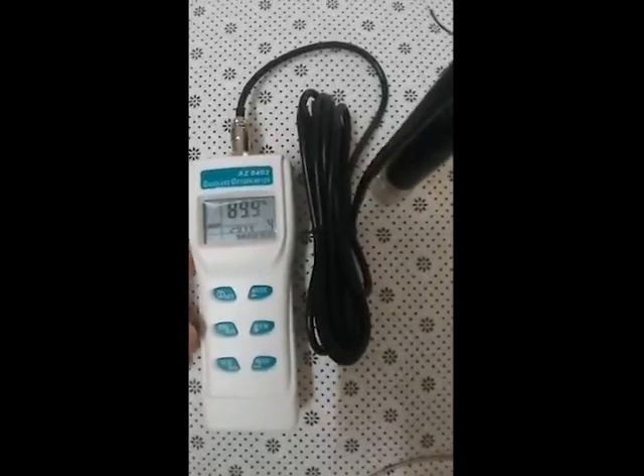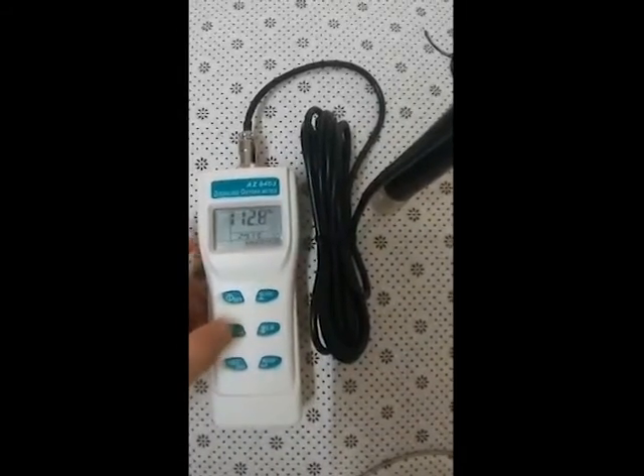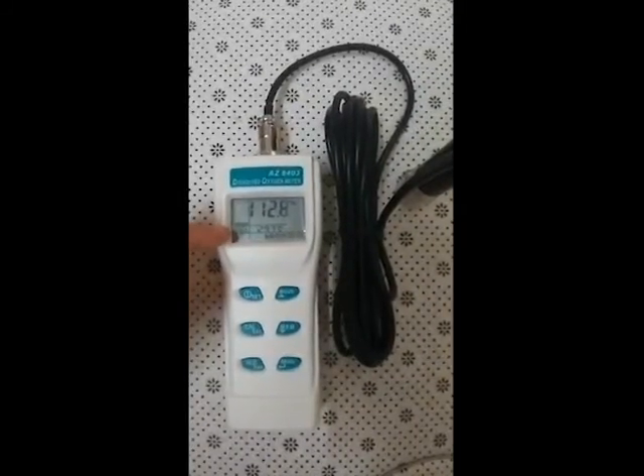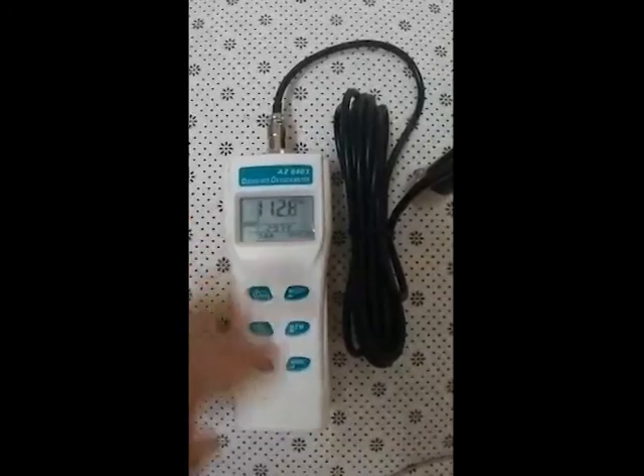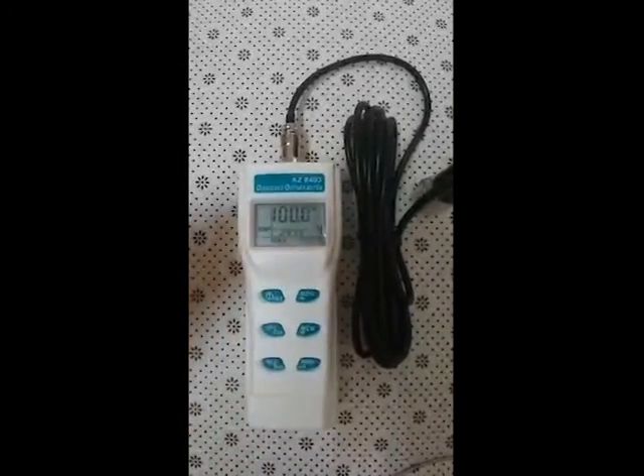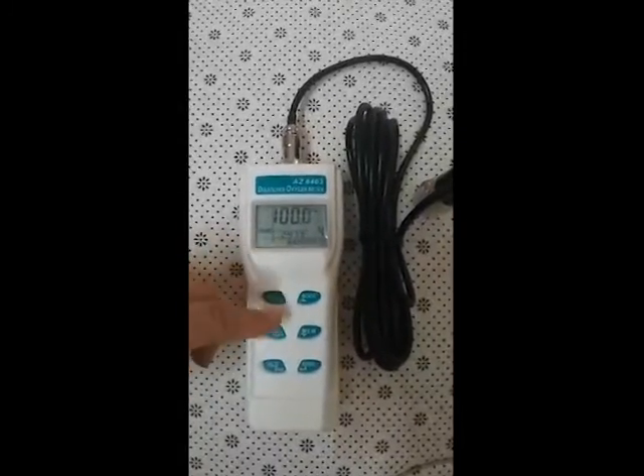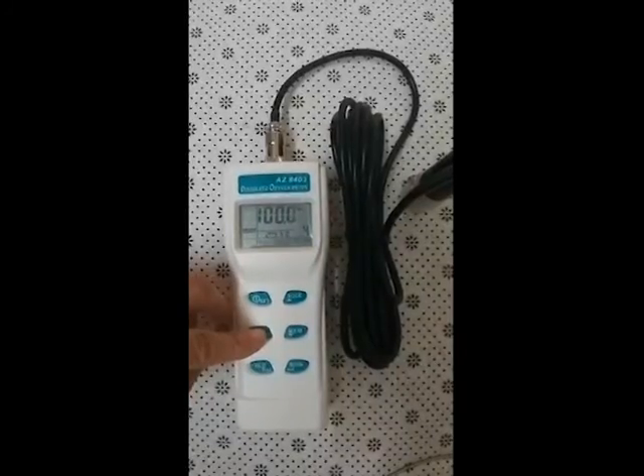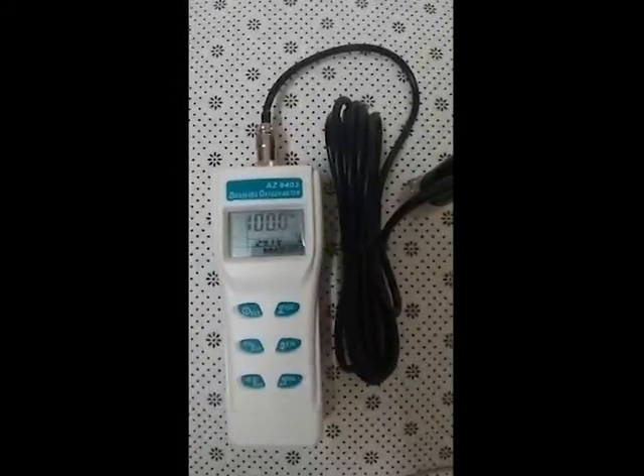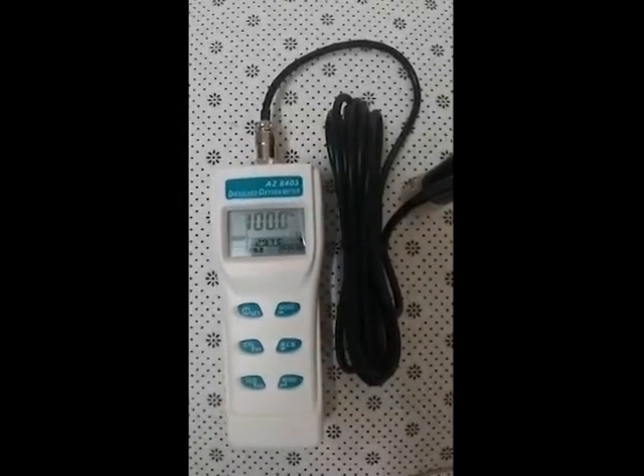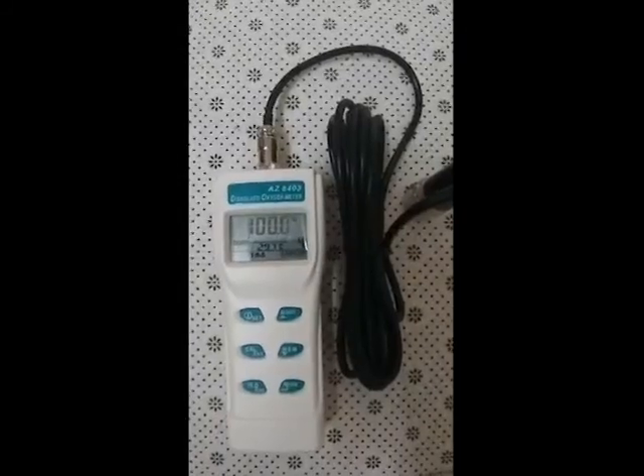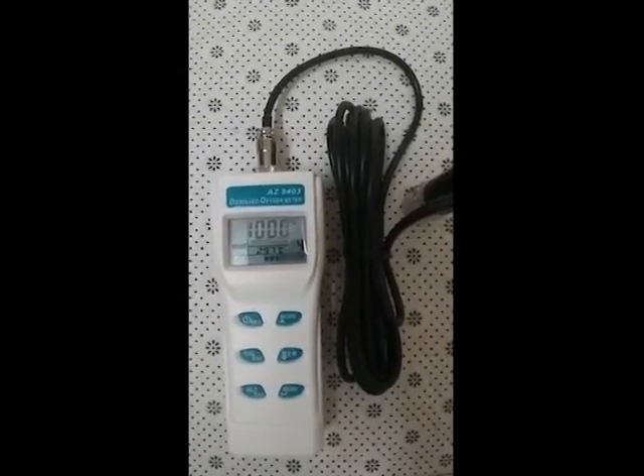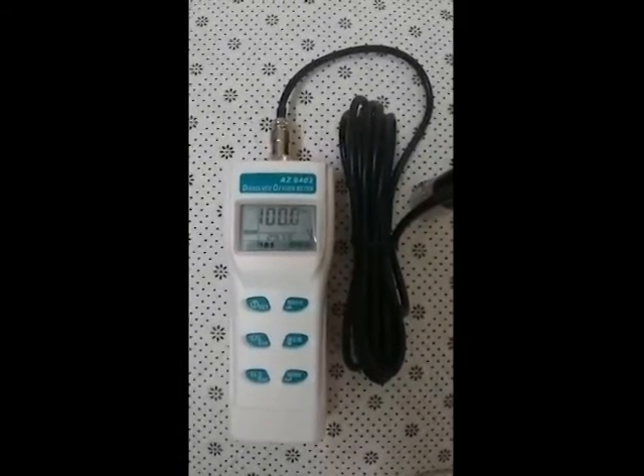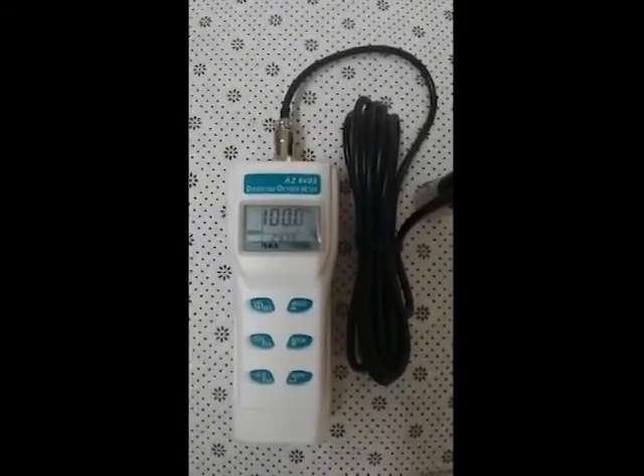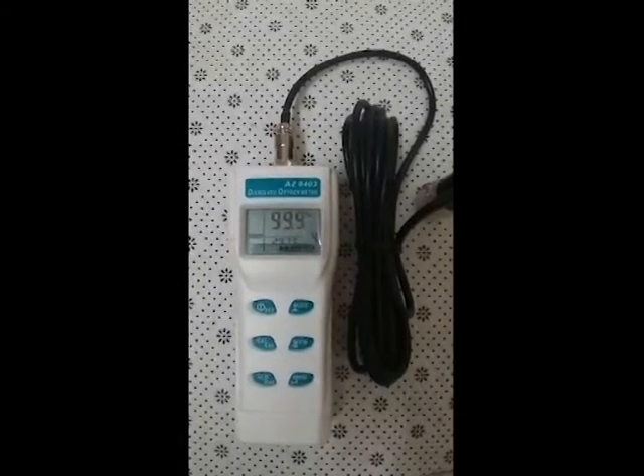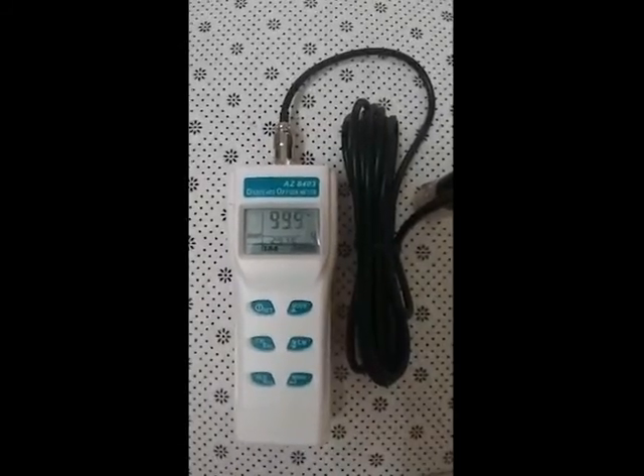After you soak the electrode, you can do the calibration, and the value will be showing, ready to be calibrated. When the value is ready, then you click enter. When you click enter, it will automatically calibrate to 100. This one I will do again together with you when we are doing the training. Or you can do the calibration yourself every time when the system is not showing 100%. When you turn on the system for about 15 minutes, you can preheat your system when the value is not 100%, before your testing. So after it finishes the calibration, you can start your testing.